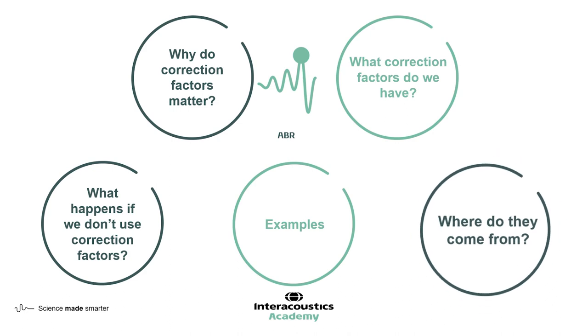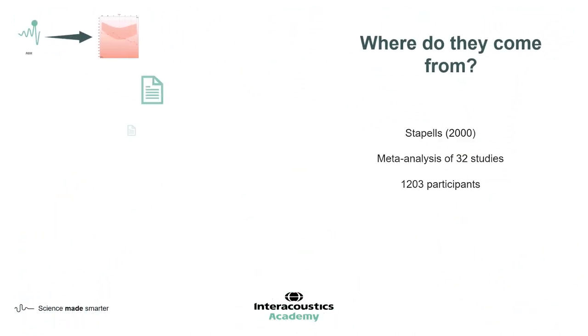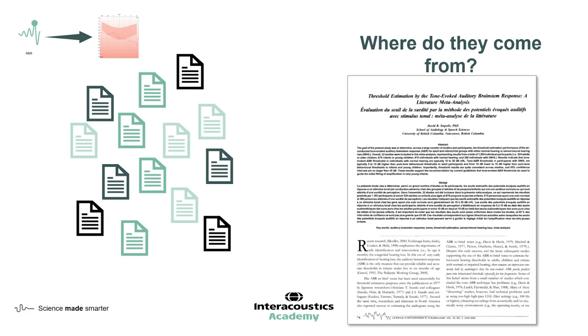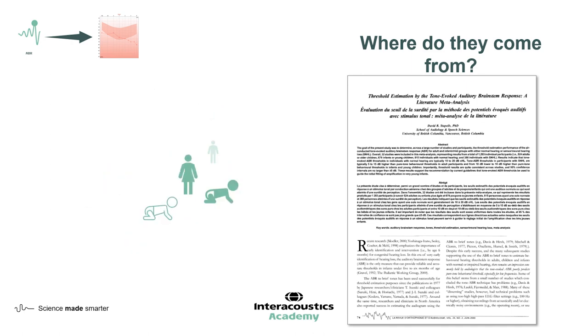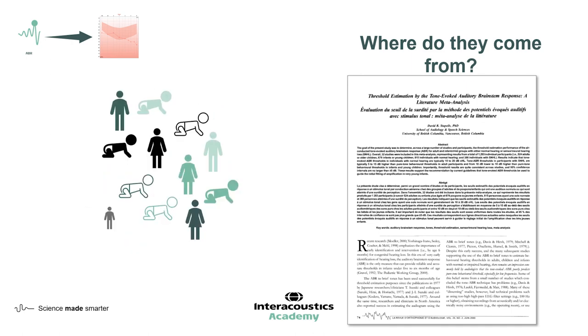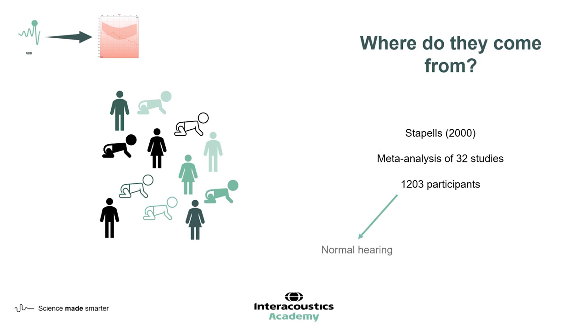Where do these ABR correction factors come from? Firstly, let's consider the ABR offset. There have been many studies over the years investigating the relationship between ABR results and pure tone audiogram or behavioural thresholds. Fortunately, Stapells in 2000 published a meta-analysis, which included 32 studies and over 1,200 participants. Some of these participants were adults and some were children. Some had normal hearing and some had a hearing loss — so we have a really comprehensive meta-analysis here.